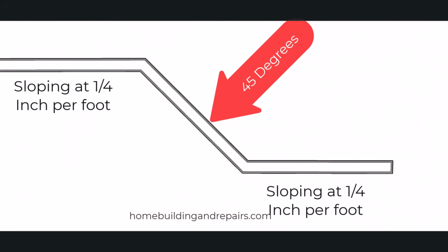Well, if you have enough fall to slope your pipes at 1/4 inch per foot, you usually have enough fall to use a 45 degree fitting and create a proper vertical offset instead. It's safer, it's quieter, and it manages the flow better.